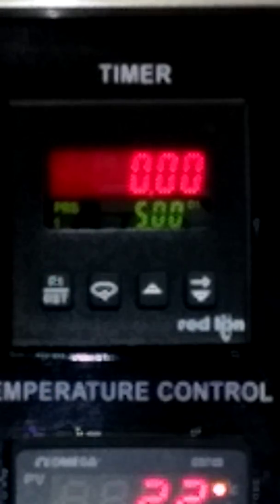Now you're back to the beginning. To save all your changes, you hold the enter button down until it says save, and then you're right back where you started. Hit the F1 reset and you should start counting up. I have a temperature controller in series with this timer with an alarm output that enables the controller, so at this time it's not counting because I've not reached my parameters on the PID controller.